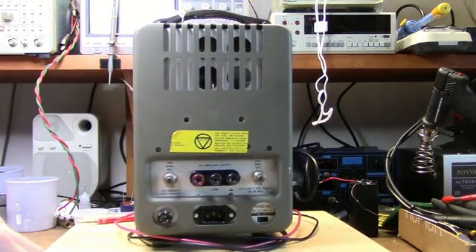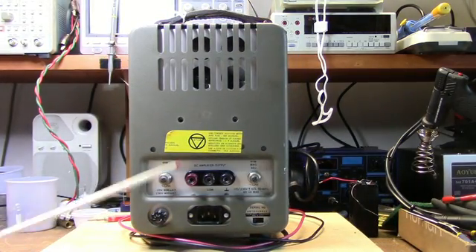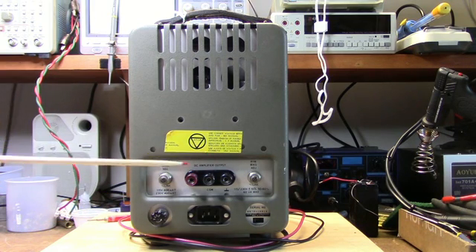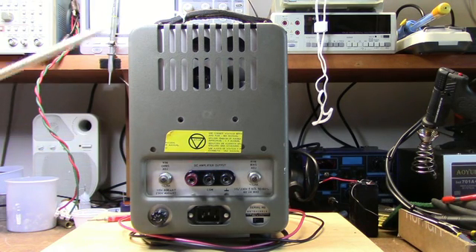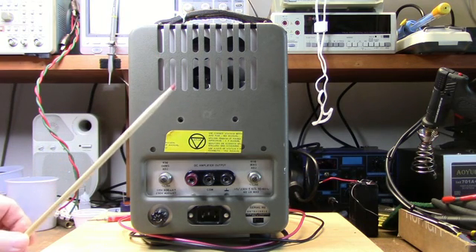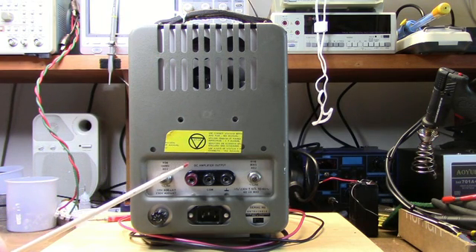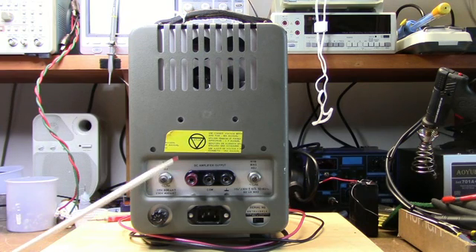Another thing this meter has is the DC amplifier output. These terminals here can feed an output device such as a chart recorder, and it will provide up to 1 volt out at full scale, and it'll drive up to 1 milliamp. So that could be useful if you want to drive some type of a recorder or a data logger of some type.